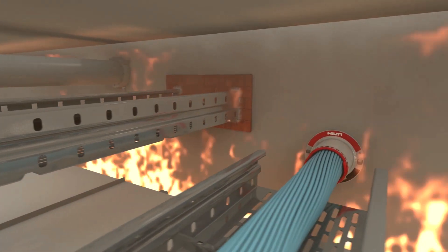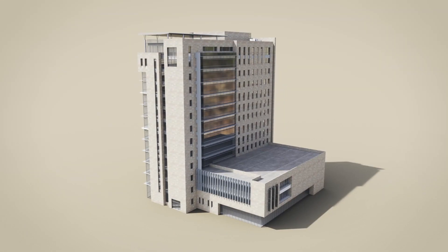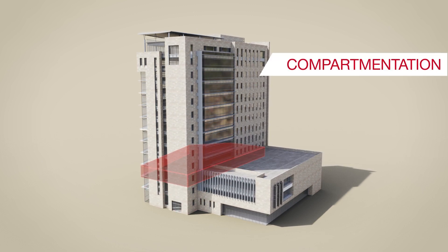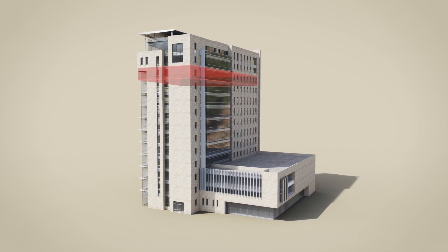To help prevent fire and smoke from spreading through buildings within minutes, all penetrations through walls and floors must be fire stopped. This design principle is called compartmentation, aiming to prevent fire spreading beyond where it started. All fire stop products used should be tested and approved.